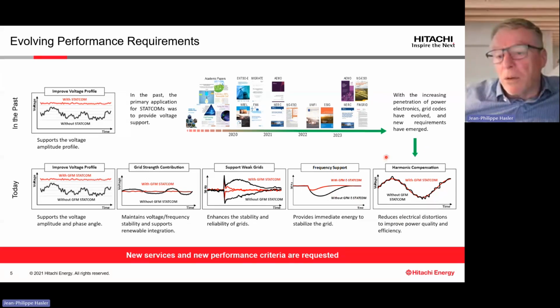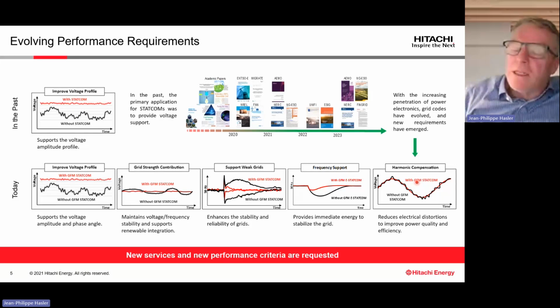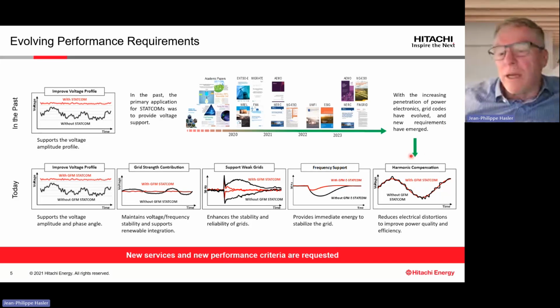And then maybe the most important is harmonic compensation, but mainly it is to avoid or to damp impedance resonance you may get in the system. Because when you have a long cable having some capacitance, or many filters or capacitor banks, all of these devices create some resonance in the system. And it's very common nowadays to get resonance at the second harmonic, between the second harmonic and the third, fourth, and fifth harmonics. And one role of the STATCOM is not really to damp the harmonic level, but rather to damp the impedance resonance.